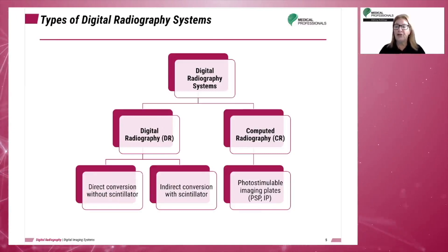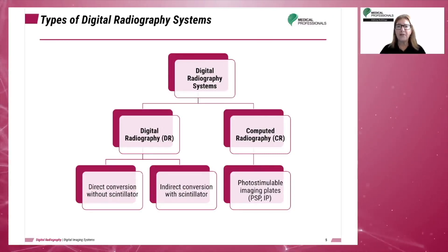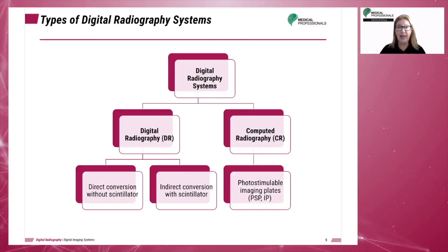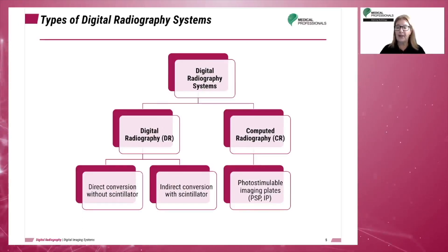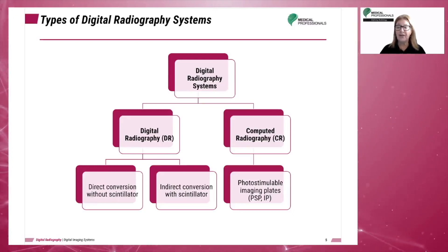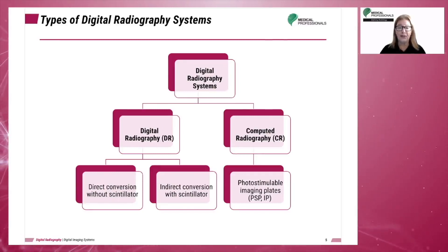Digital radiography, or DR, usually refers to an image receptor that may be inside a device bearing some resemblance to a traditional cassette, or the image receptor may be part of the X-ray equipment itself and never handled by the radiographer. In either case, once the exposure is taken, the image data is sent to a computer and the image receptor is immediately ready for the next exposure. DR uses flat panel detectors with thin film transistor technology that are categorized as direct capture or indirect capture.